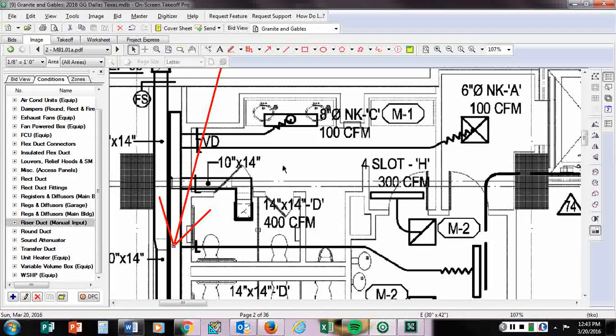Pretty straightforward. A bathroom is going to be at a negative pressure to the hallway right next to it. So here's the hallway right here. We're going to be putting in less supply air via this register than we are exhausting out via this register right here.